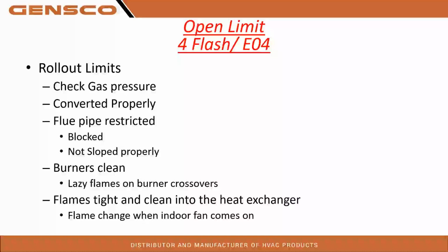So we're going to make sure every time we touch a unit that it's clean and it's doing what it should be doing in the process, right? So we're going to look for flames tight and clean into the heat exchanger, so no disruption in flames when the blower comes on.